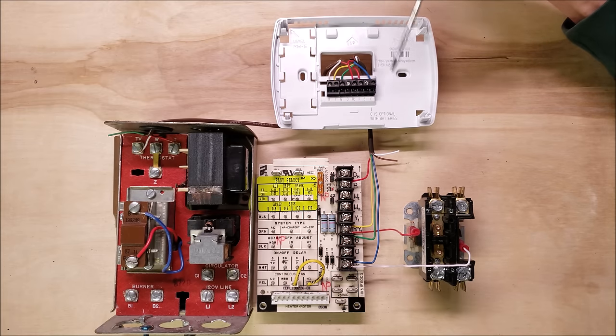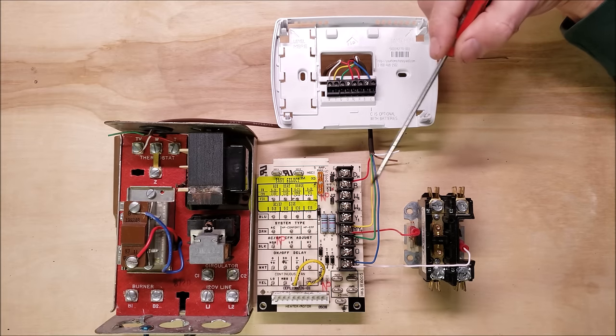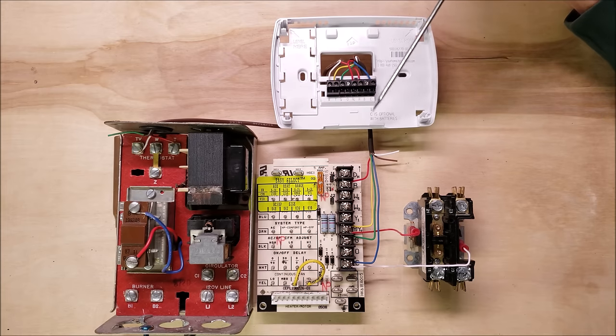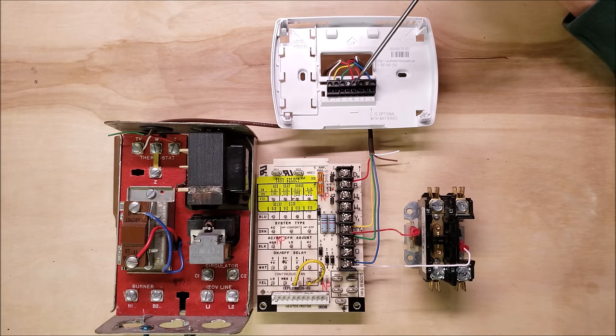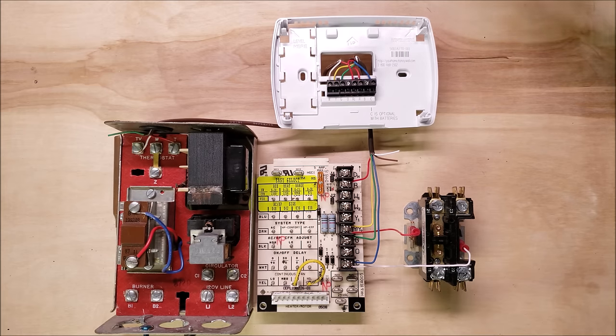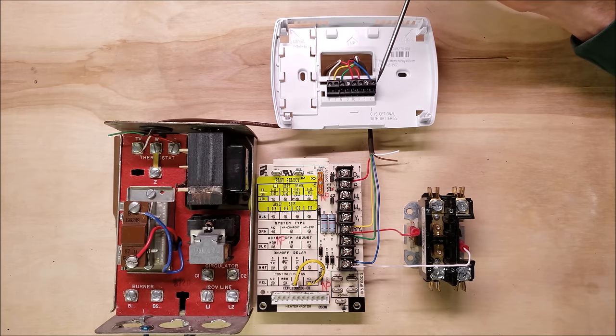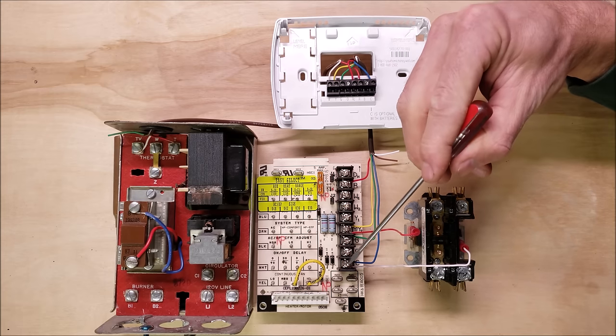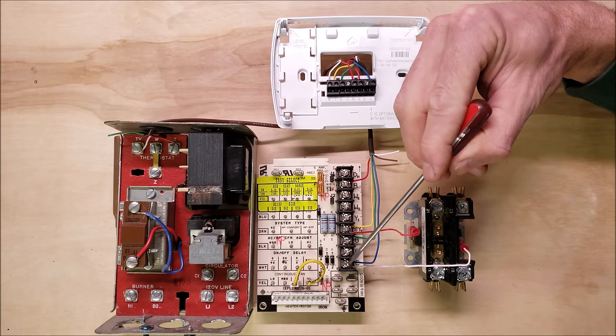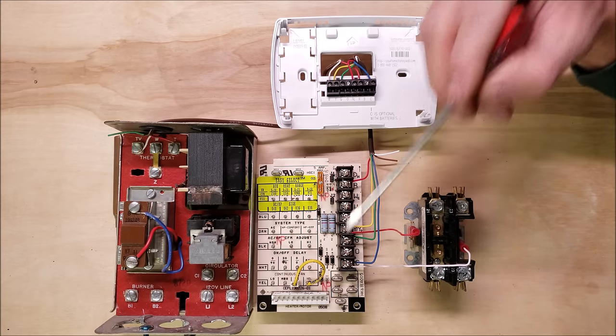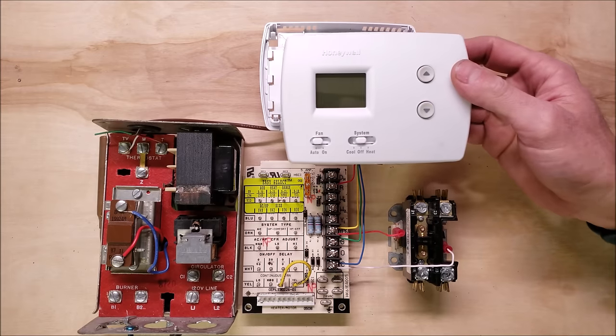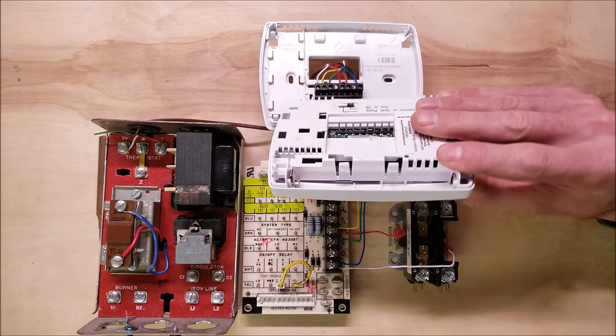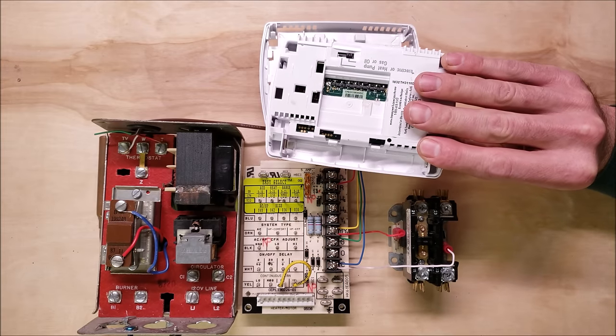Same thing in the thermostat where you have your 24 volts coming from R, it gets connected to RC for your air conditioner. To power the thermostat face, it's going to go through the thermostat face and find its way back through the C and come back over to the control board on C or to the C on the transformer. The thermostat is off because there's no batteries in the back of this.